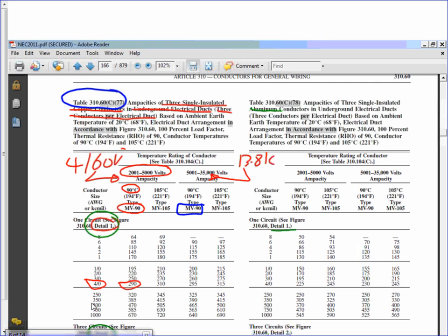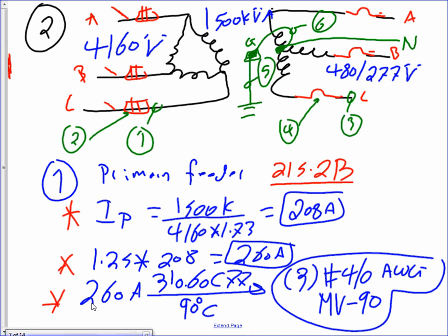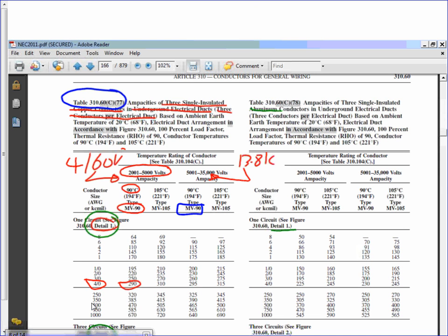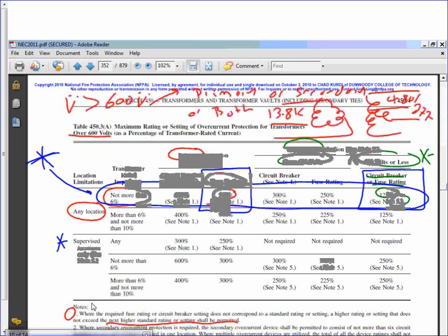So everybody knows where we came up. You can't believe how many times over the years I taught, and at the end, when the students sit the test, they go to 310.15(B)(16). You don't go to 310.15(B)(16) if the voltage is higher than 600 volts. You can't go there. If you look at it, you can't go there. Okay, so we got that one. Everybody knows why we went to 310.60, 310.60(C)(77)(90). All right, so we got that under control.